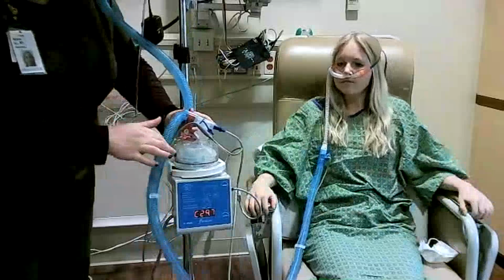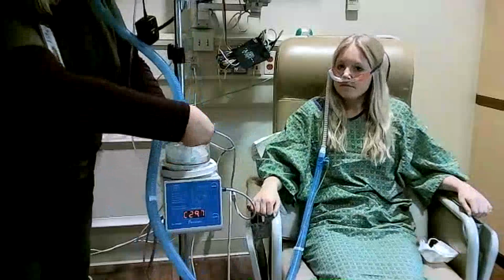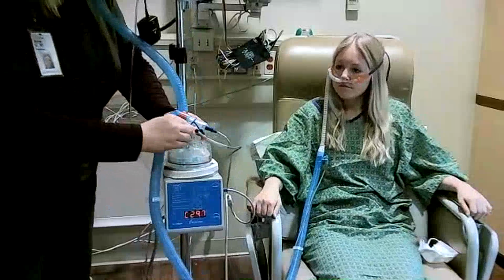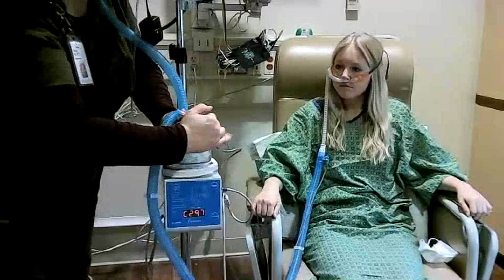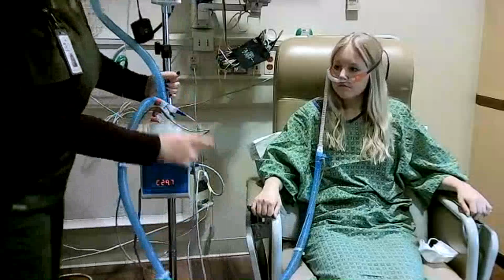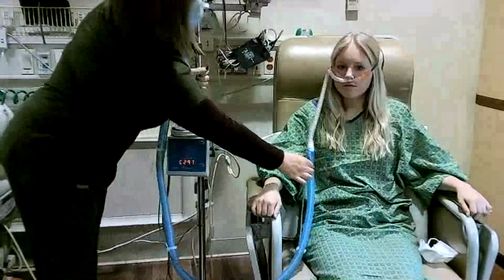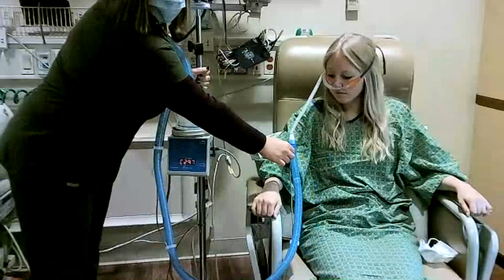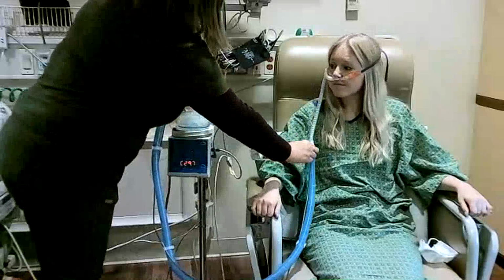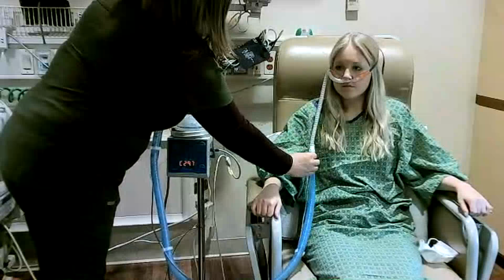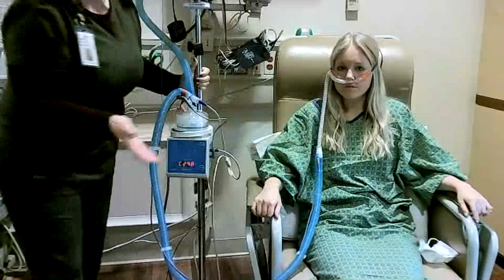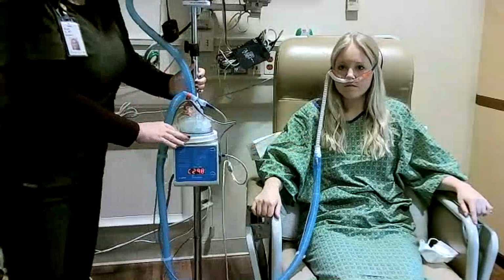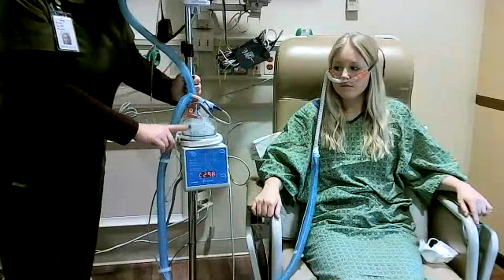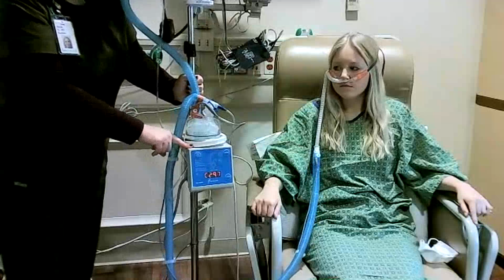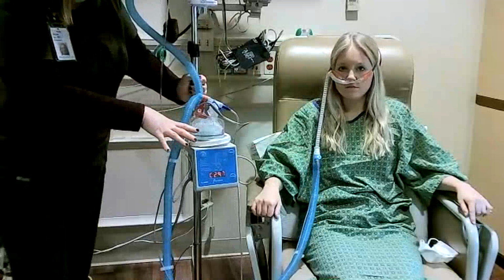Other common alarms might be for your temperature probe. Less commonly, this one can come loose. Just put it back in nice and tight. There's another temperature probe right up here, right by our patient. That one can sometimes come loose as well, and that'll give you an alarm. So if you just kind of squeeze that back in there and make sure that's in there tight, that should solve most of your alarms. If you're still having alarm issues, call your respiratory therapist. We'll get to you as quickly as we can to help you troubleshoot that.